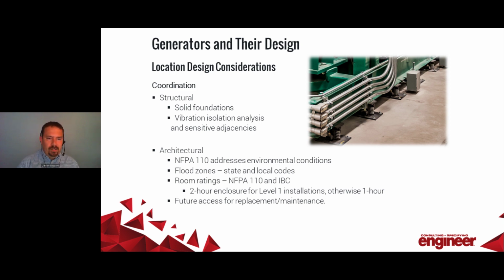On the architectural side, it's making sure that we're addressing the environmental conditions found in NFPA 110, which talks about the rating of the room, protection for fuel lines coming into the building, shafts for exhaust up through a building, and so on and so forth. Floodplains. Are we installing a generator in a basement level that falls within a floodplain? A lot of state and local codes require supporting design to ensure that, if we're installing in the floodplain, we minimize the risk of damage from flooding, from sewer backups, those kinds of things. So it's important that we consider all of that as we're finding a location for our generator.